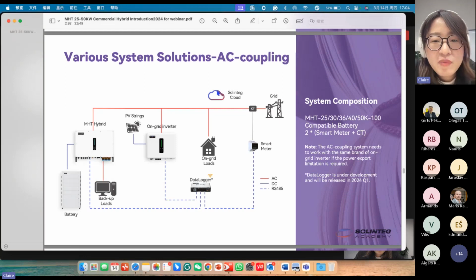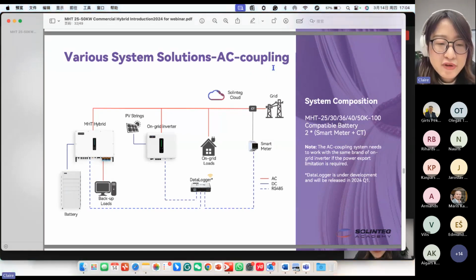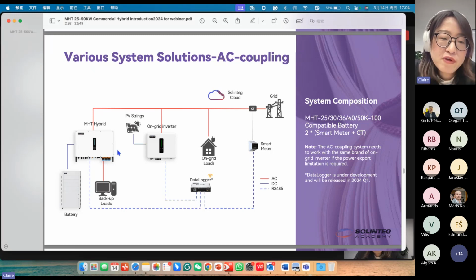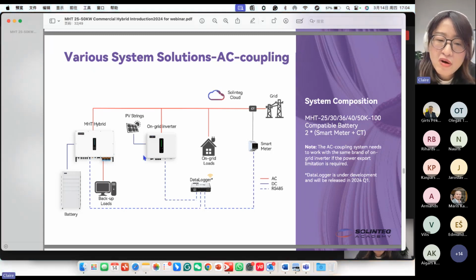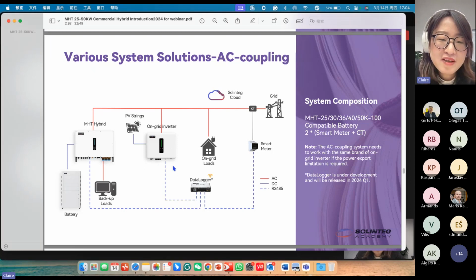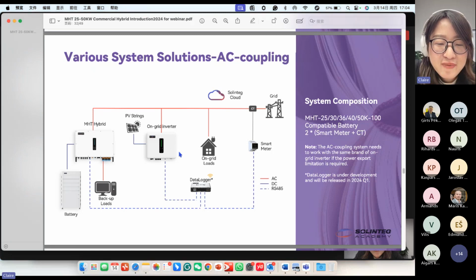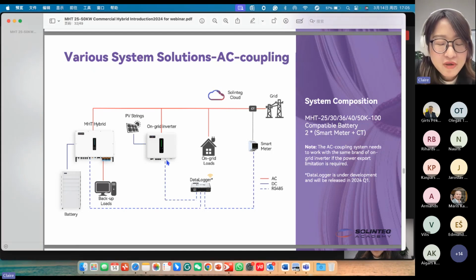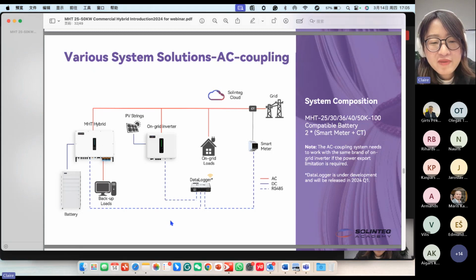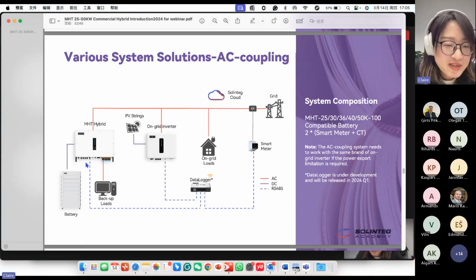And then we can also be used in the AC coupling situation. For the AC coupling situation, if the customer uses a Solinteg on-grid inverter, we can realize the power export limitation. But if you use a third-party on-grid inverter, currently we cannot realize the power export limitation because we cannot control the output power of the third-party inverter. But if the company can share their protocol with us, and we can integrate their protocol into our data logger, we can also control this third-party inverter's output power. So at that time, we can also realize the export limitation for the combination of a Solinteg hybrid and a third-party on-grid inverter.